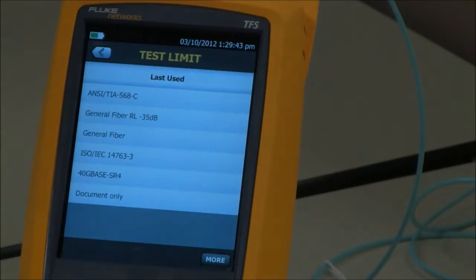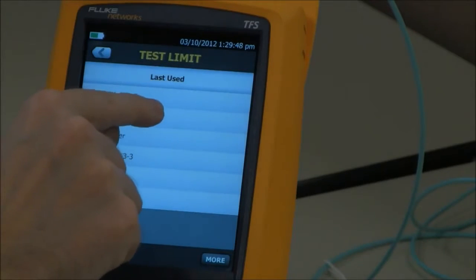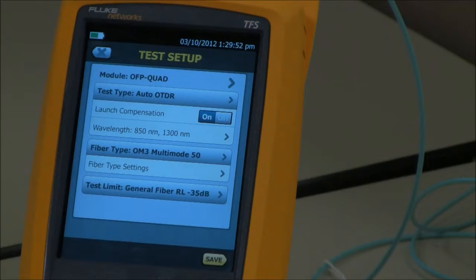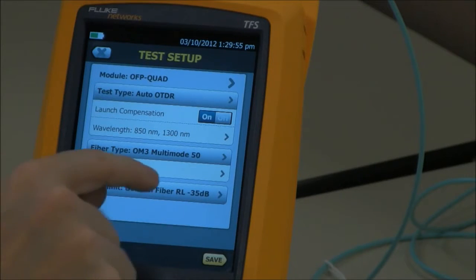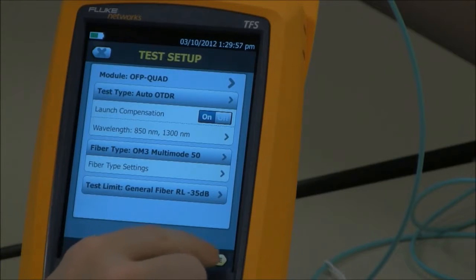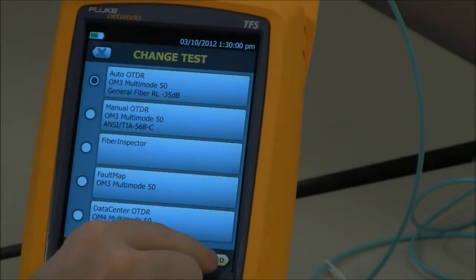I'm going to change the test limit and select something called General Fiber RL minus 35. That's going to have the same values as that TIA test, except we're now going to set a limit for reflectance, and that's going to be minus 35 dB.